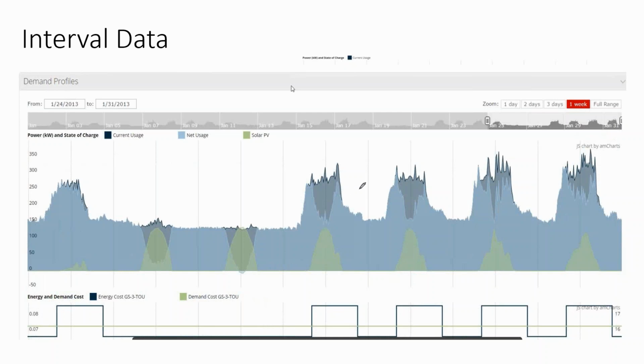Well, now we can take this debate one step further and say, let's add a battery here and start shaving off the shoulder peaks in the morning and in the evening, actually achieving our demand reduction. Now, what this also suggests is that there is an optimization point, because we notice these shoulder peaks in the morning and the evening are now spiky.